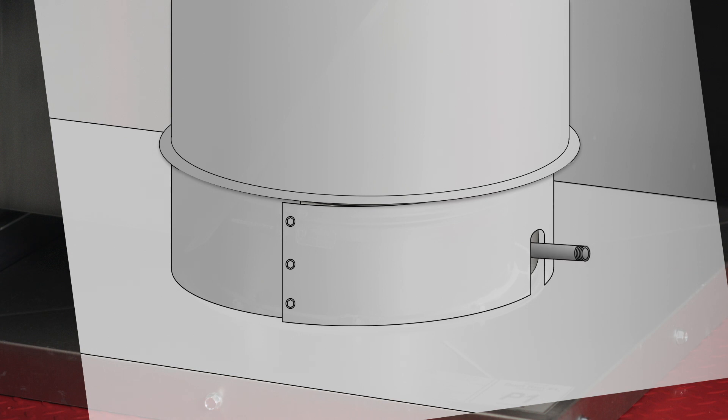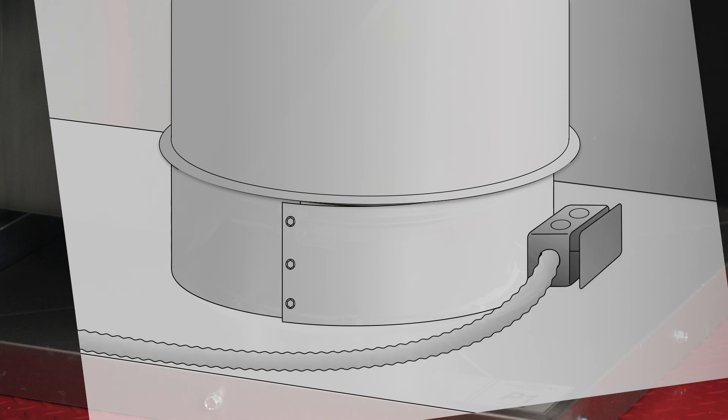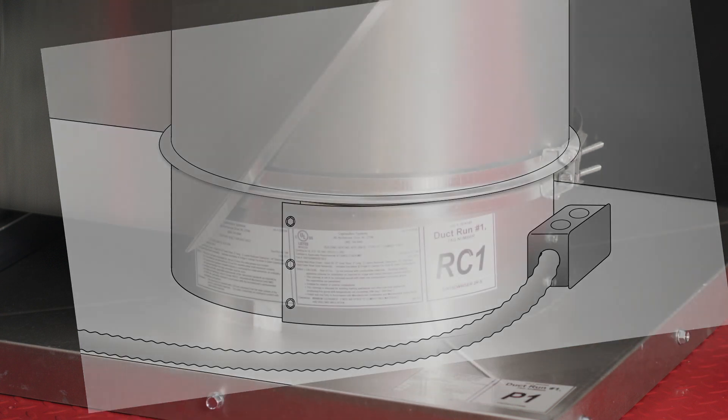When a wiring extension for the sensors is needed, install a nipple from the inner duct to a junction box just outside the riser cover, as shown. Never install a junction box inside the riser cover.